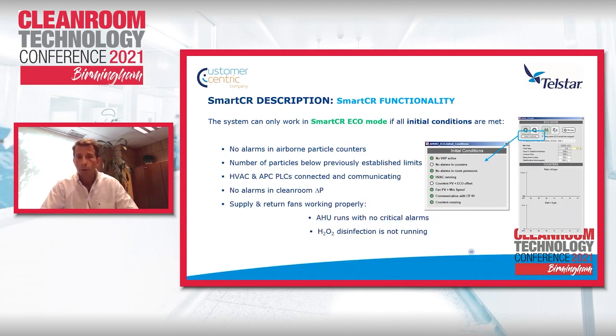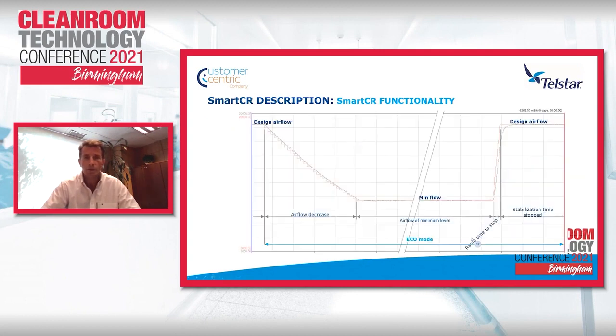A smart eco mode obviously has a set of initial conditions to start. It will not start if we have any airborne particles alarm in the rooms, so we will keep the conventional situation. It will not start if we have any alarm in the clean rooms or about the differential pressure. It will not start if we are not getting the right communication among the different PLCs. It will not start, for instance, if we have started a peroxide disinfection mode of the HVAC. These are common sense criteria.